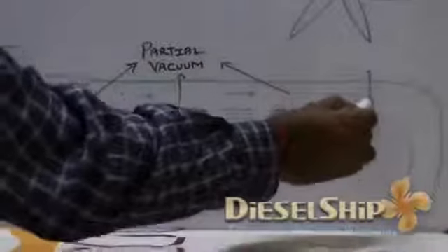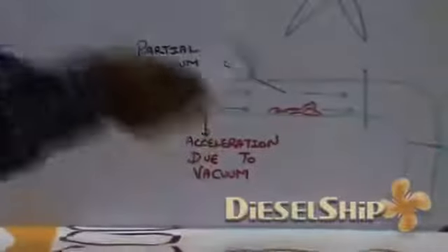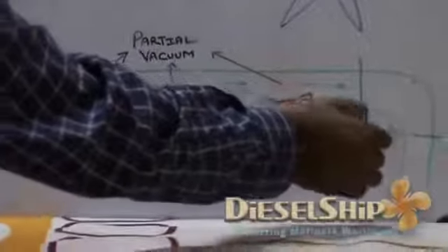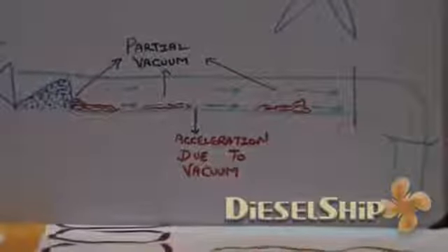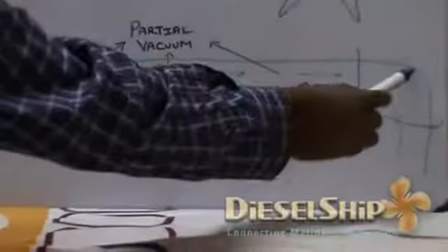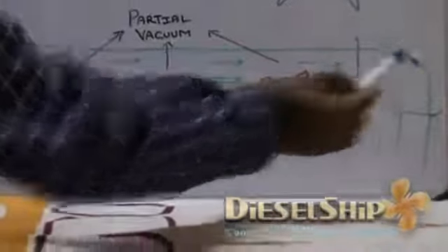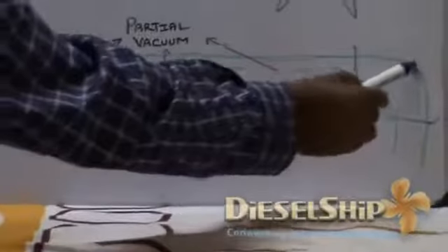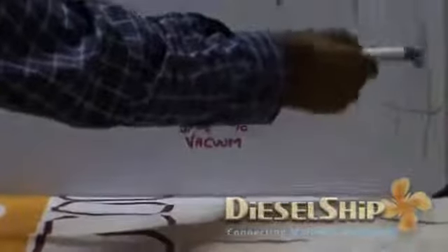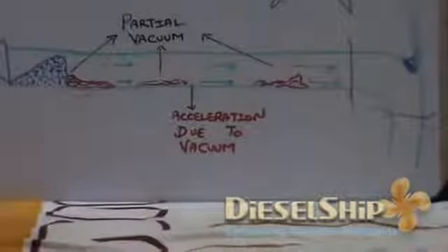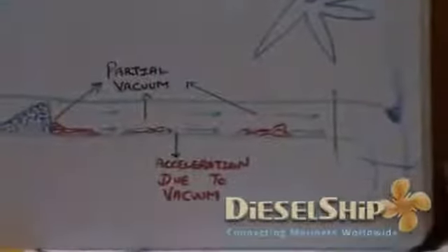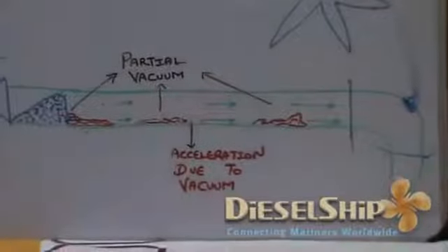And let's say if you have a joint over here or gasket, you definitely will have a blowout either from the gaskets first, and after such banging over a period of time, the material over here becomes weak, and thus the steam starts to blow out through this. So this is called as the condensation induced water hammer.